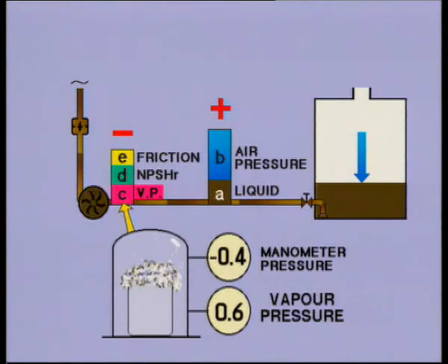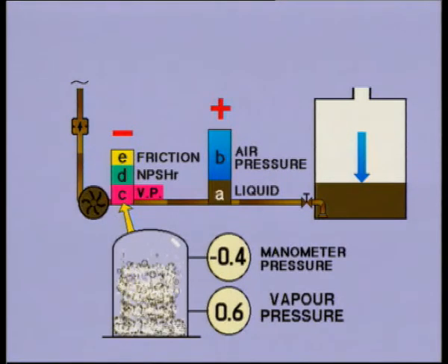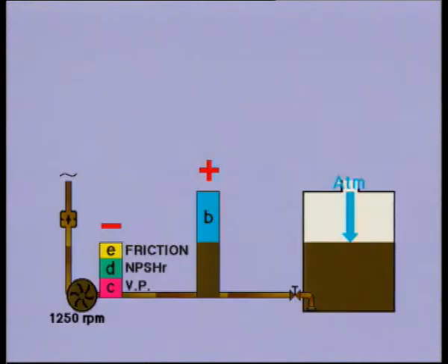You should avoid operating pumps at such a low pressure, where oil gases off. If you don't, they will cavitate, lose capacity, and be permanently damaged. Note that the suction lines are not flush with the tank floor. Pumps and the discharge lines in our vessel are mounted more than 2 meters above the bottoms of the tanks. At the end of the discharge, a lift of approximately 2 meters must be taken into account and added to the minus column.